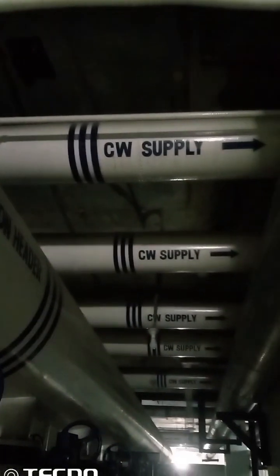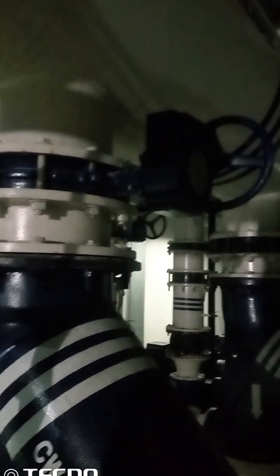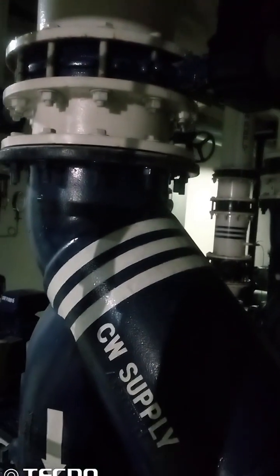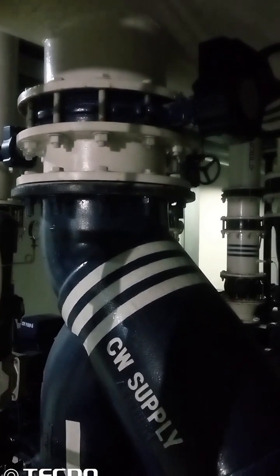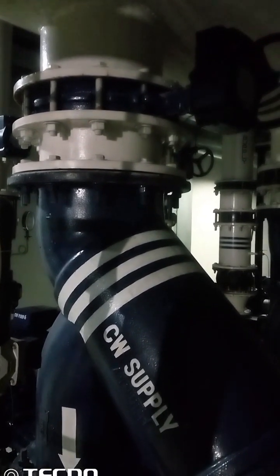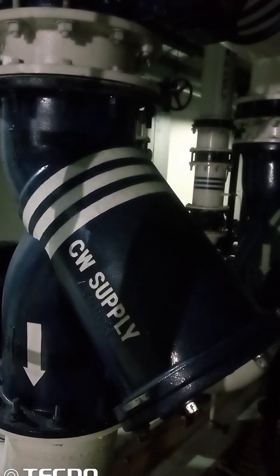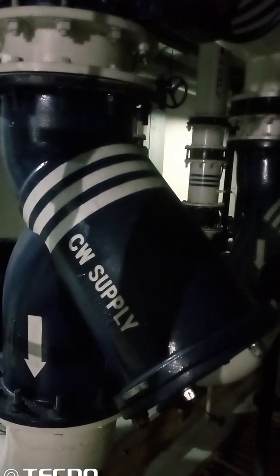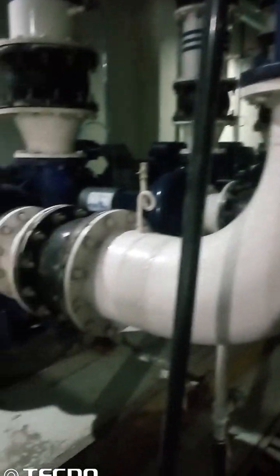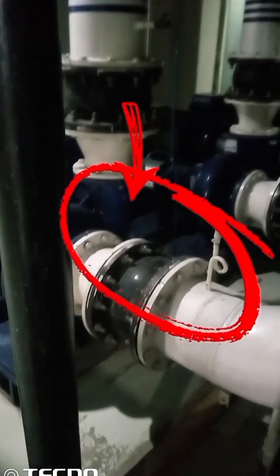Actually, various branches of the pipelines are connected or joined at a point which is called a header. So through the suction header, first of all, we have the butterfly valve. Then it comes to the strainer. What is the use of the strainer? It simply washes out the water before it goes to the pump side. You can moreover clean it when it is choked, from the bottom side. After the strainer comes the flexible, and the main job of the flexible is vibration isolation.